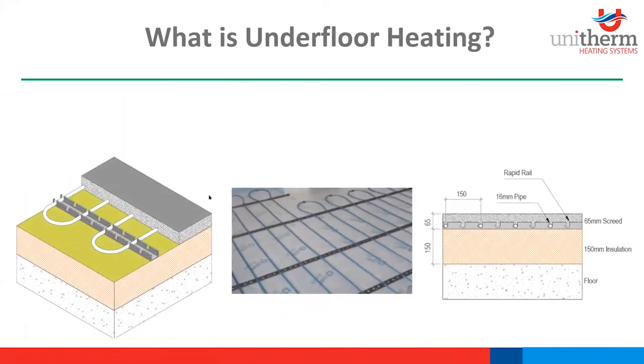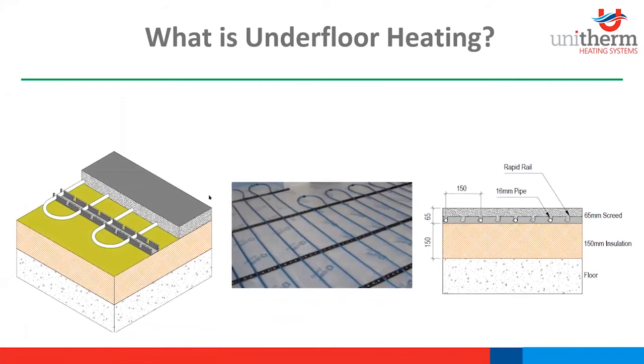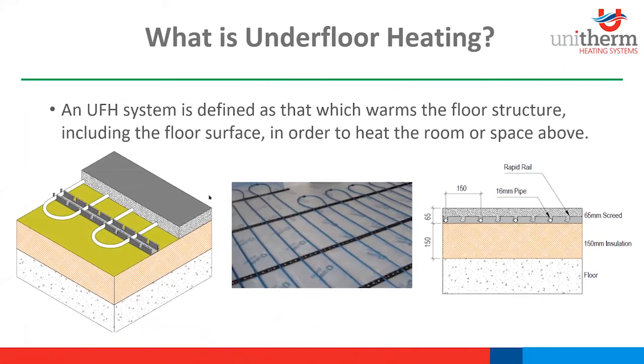Going to talk to you about underfloor heating. Just don't know the level of people here now, so just going to give you a quick run through on underfloor heating. So here we have a few section drawings of underfloor heating in a photograph. So that's 150 mil centers there, ideally 75 mil screed with your 16 mil PEX pipe, and you're generally 150 mil insulation onto your concrete slab.